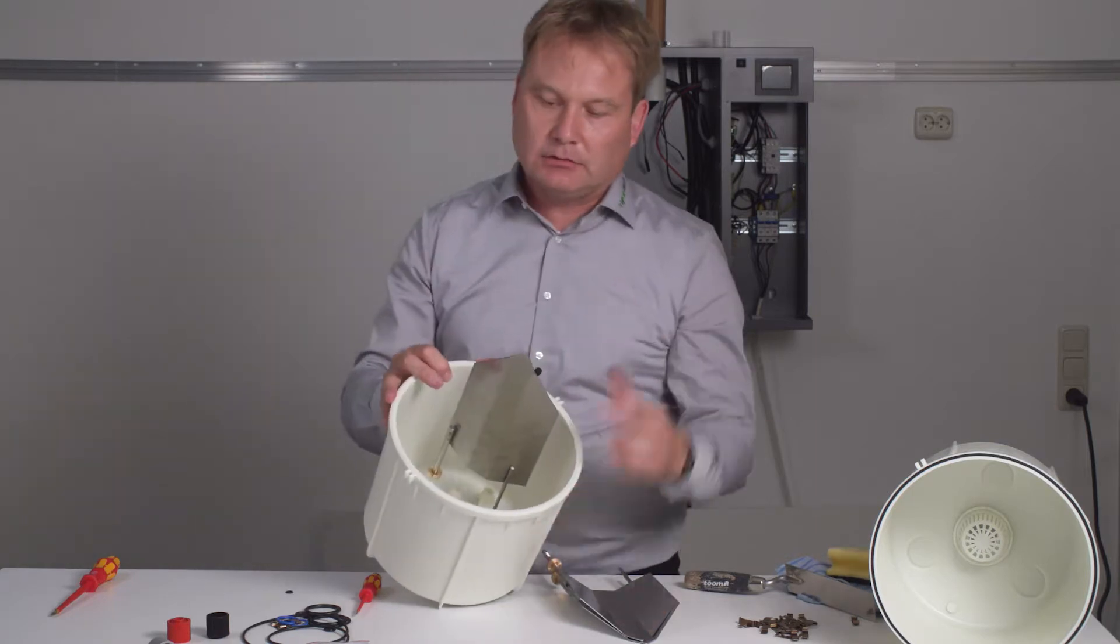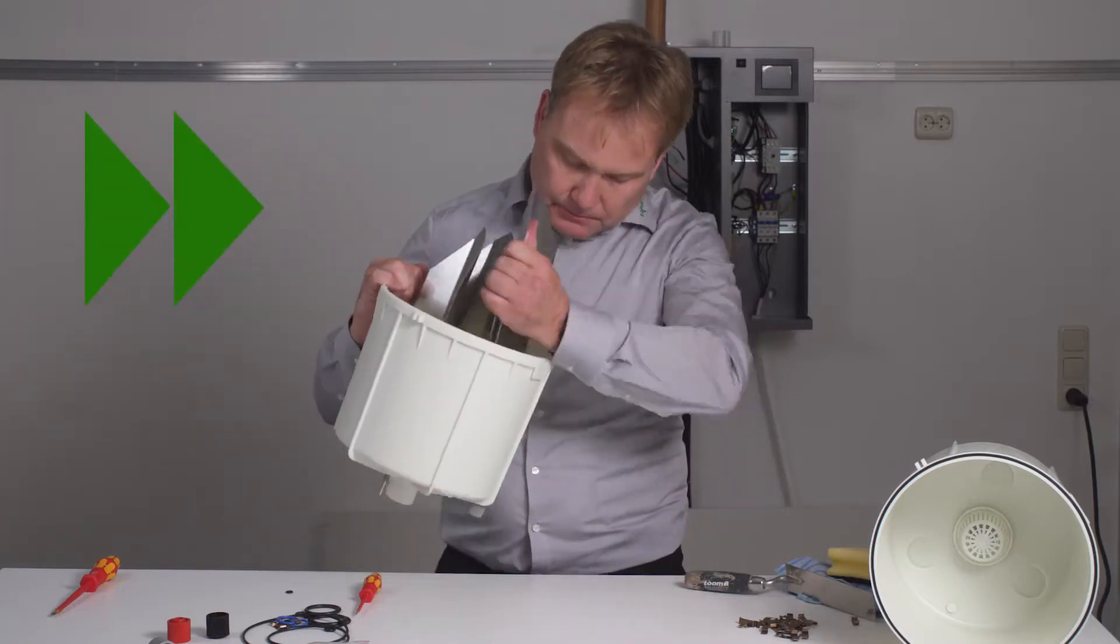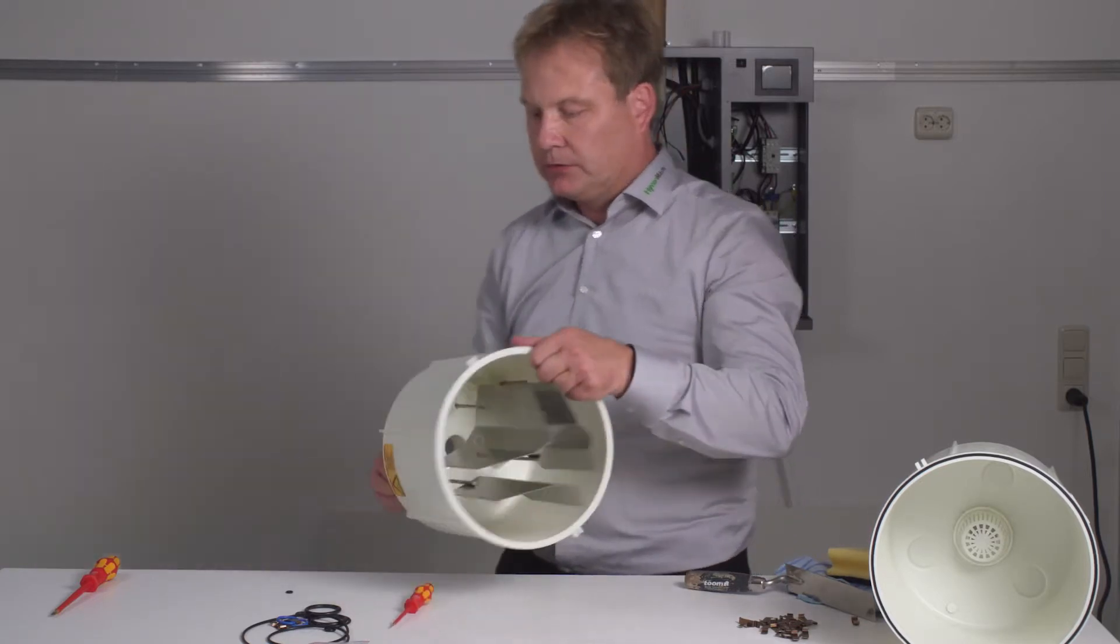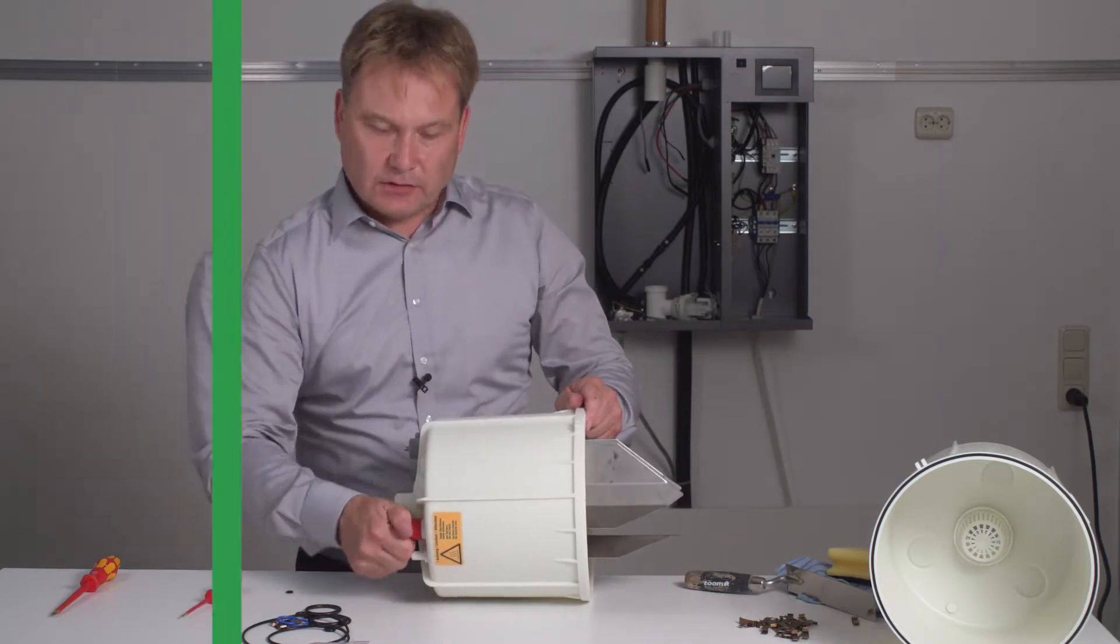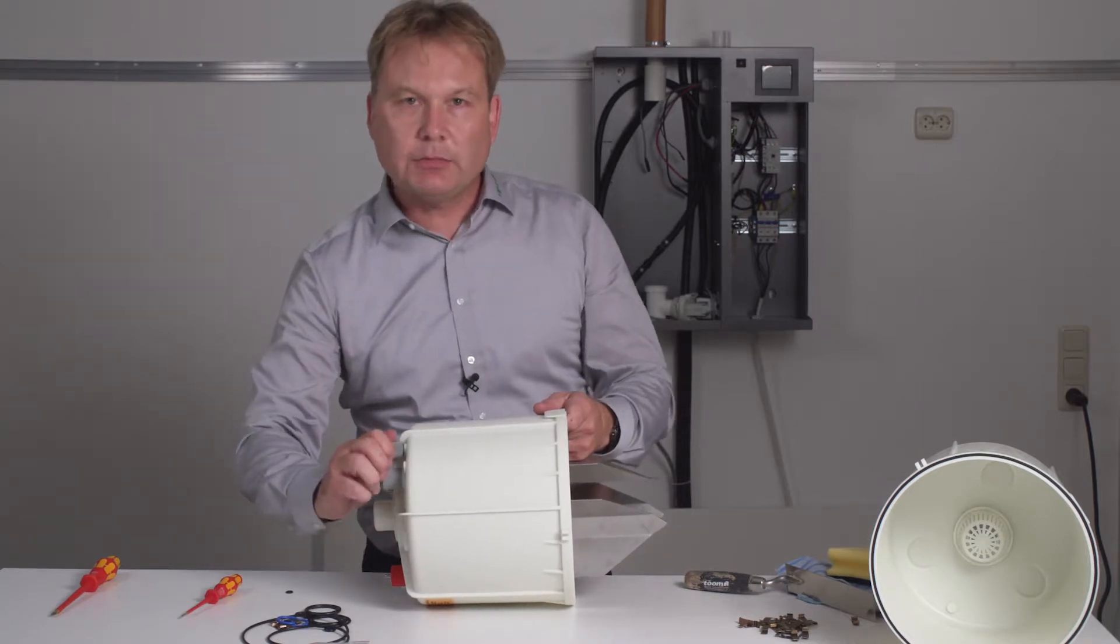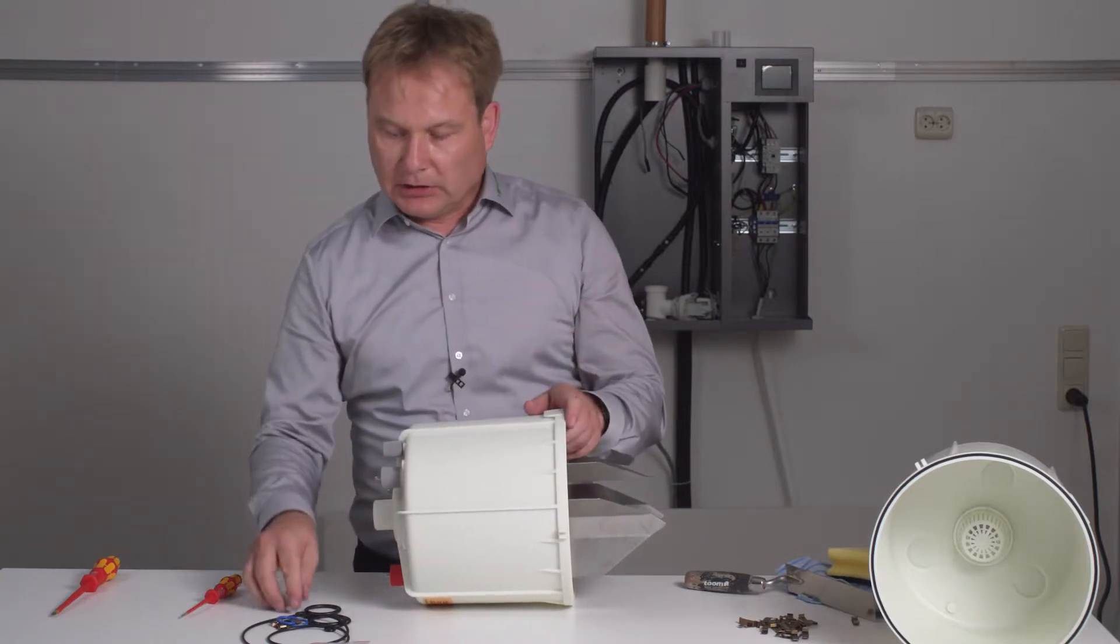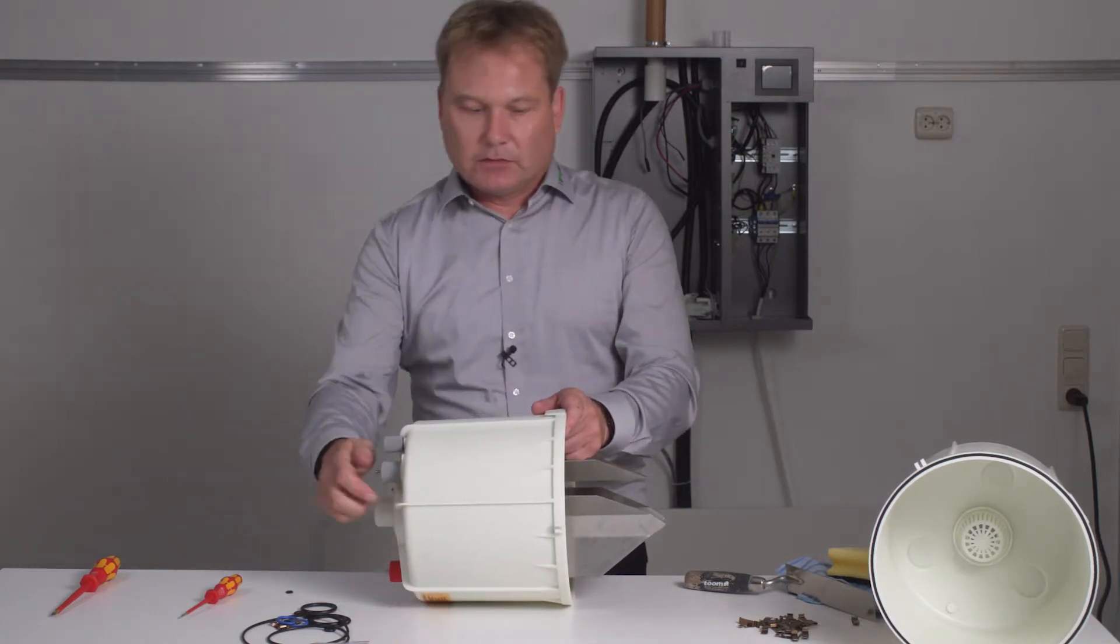Then reinsert the electrodes. Please make sure that the surfaces are always parallel to each other. And please tighten the hand nuts by hand only. Check these hand nuts at each visual inspection, half yearly visual inspection. Tighten or check if they have come loose, that can happen due to vibration. Check the O-rings as well for wear. Check if they are sitting tight. This is very important.